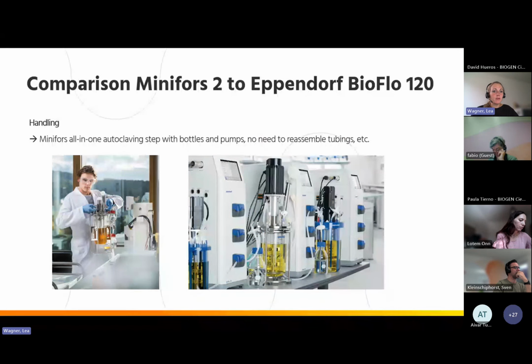Yeah, here you can see it again on this picture. So we also have the advantage, as mentioned before, of great usability, because the whole device, or the vessel, can be brought to the autoclave together with the bottles and also with the pumps. And for Eppendorf, you do not have everything attached to the vessel, so there are different parts that somehow must be transported to the autoclave, and the customer needs to reassemble tubings, etc. again after autoclaving. So with Minifors 2, the customer saves time and has less risk of errors.